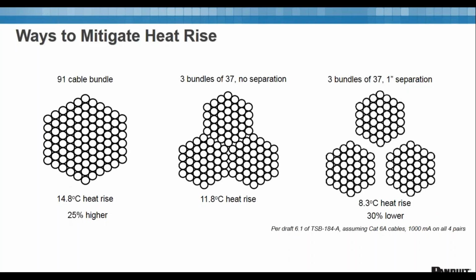If you've got a handful of cables laid in there, maybe 1, 2, 3 layers, and they're sort of loosely fitting in there, you're much closer to limiting the impact. As long as air can get to the cables, you're going to be okay. When everything's just jammed in there, you're really getting close to what looks like your typical round cable bundle. So right now I don't have a better definition for you, other than to say if the cables are packed together and you don't really think air is getting to those cables in the center, you've got a bundle on your hands.